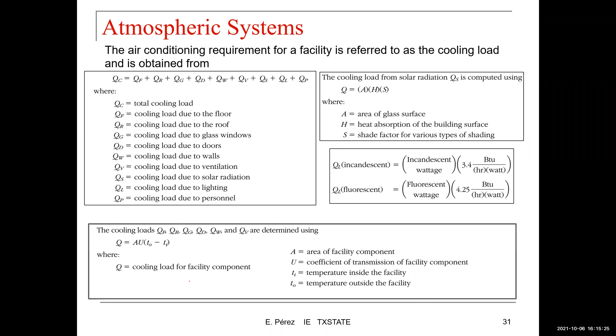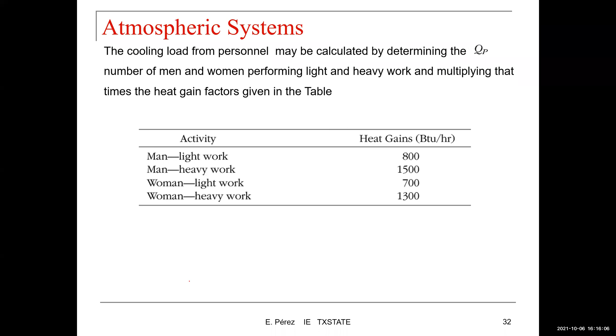And then finally, for computing QP, the cooling load due to the personnel, we'll have this standard. It depends on whether it is a man or a woman and the type of work being performed. So the cooling load from personnel may be calculated by determining the number of men and women performing light and heavy work and multiplying that times the heat gain factor given in the table. The heat gain factor depends again on the type of work performed and also on the gender.